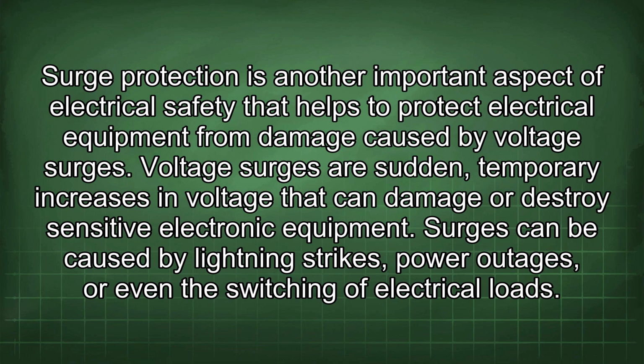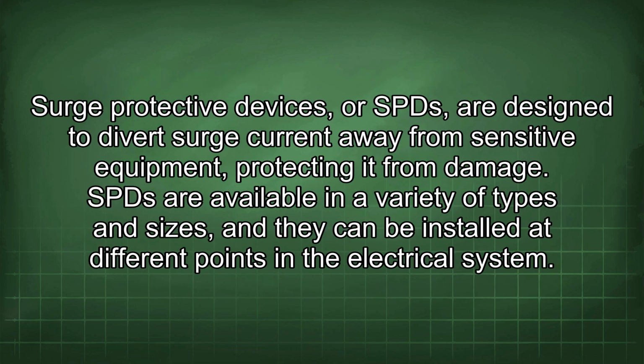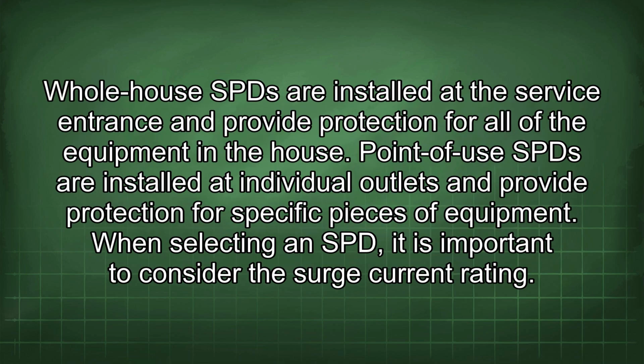Surge protection is another important aspect of electrical safety that helps to protect electrical equipment from damage caused by voltage surges. Voltage surges are sudden, temporary increases in voltage that can damage or destroy sensitive electronic equipment. Surges can be caused by lightning strikes, power outages, or even the switching of electrical loads. Surge protective devices, or SPDs, are designed to divert surge current away from sensitive equipment, protecting it from damage. SPDs are available in a variety of types and sizes, and they can be installed at different points in the electrical system. Whole house SPDs are installed at the service entrance and provide protection for all of the equipment in the house. Point of use SPDs are installed at individual outlets and provide protection for specific pieces of equipment.